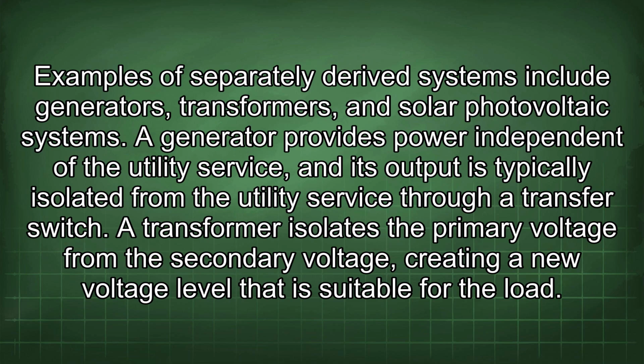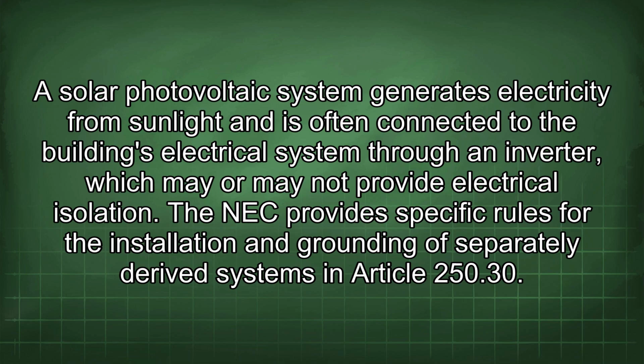Examples of separately derived systems include generators, transformers, and solar photovoltaic systems. A generator provides power independent of the utility service, and its output is typically isolated from the utility service through a transfer switch. A transformer isolates the primary voltage from the secondary voltage, creating a new voltage level that is suitable for the load. A solar photovoltaic system generates electricity from sunlight and is often connected to the building's electrical system through an inverter, which may or may not provide electrical isolation.